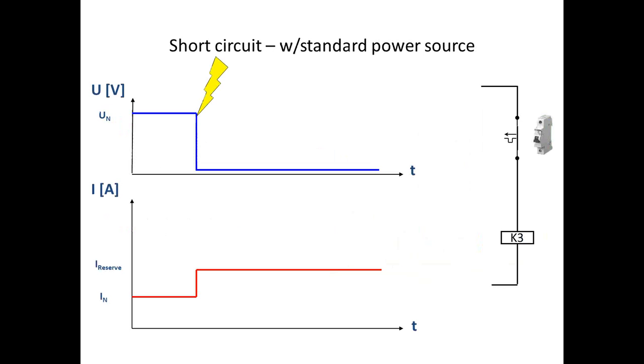Here's an example of what happens when a standard power supply is not sized correctly. The voltage will dip, as shown in the blue line, and the current rises to where it can, and the breaker does not trip. If the power supply protects itself from the short, the breaker will not even trip using its thermal properties.